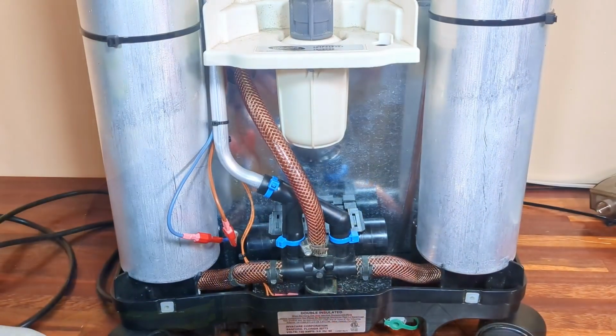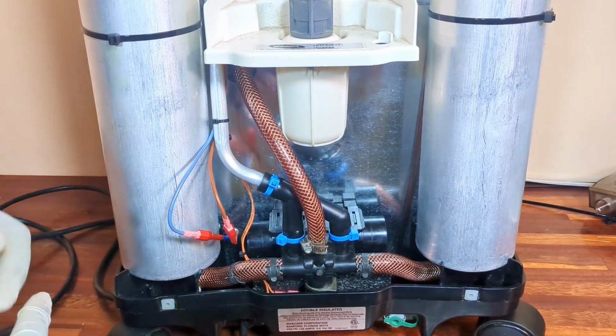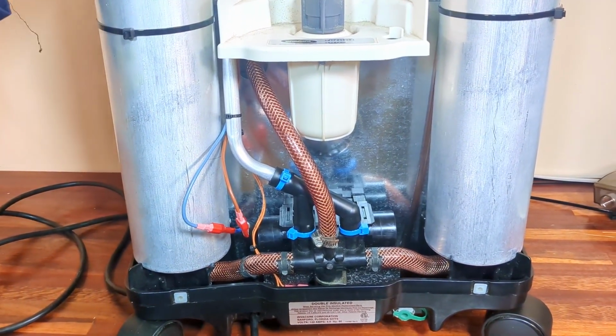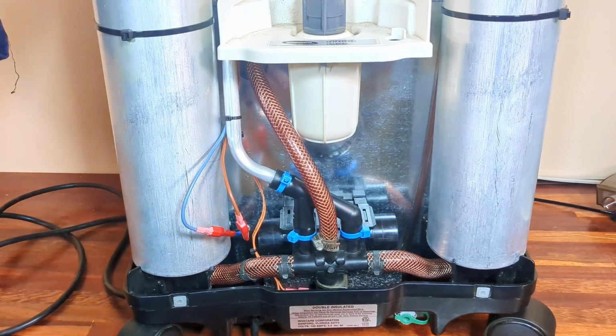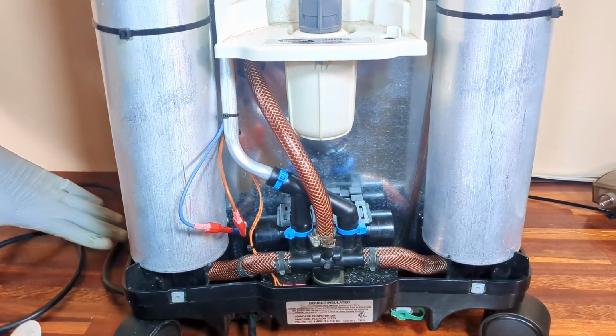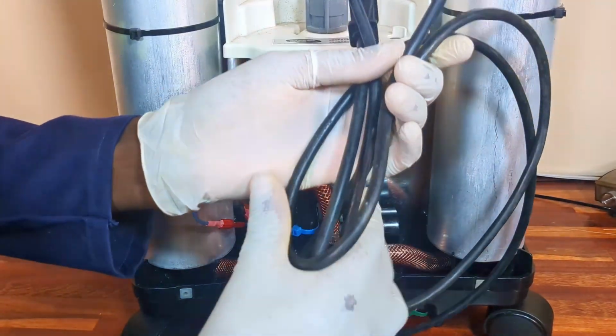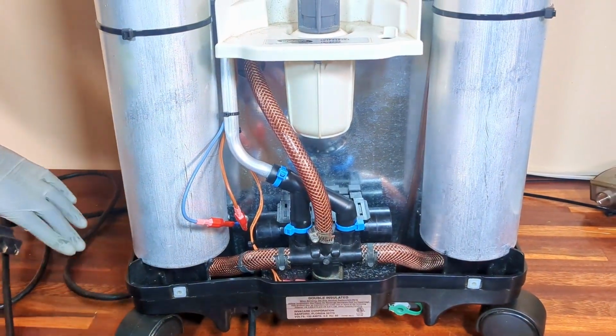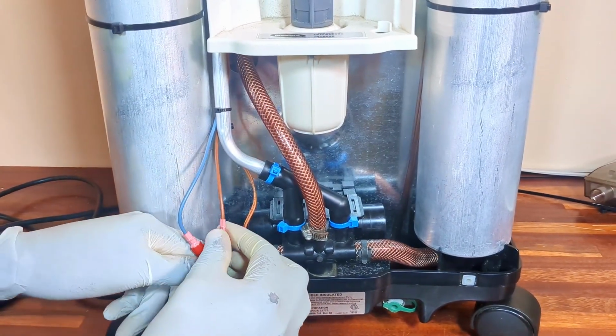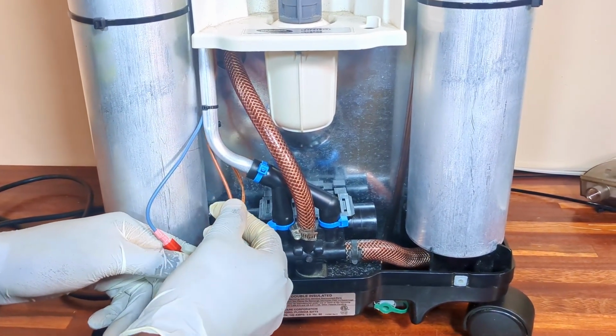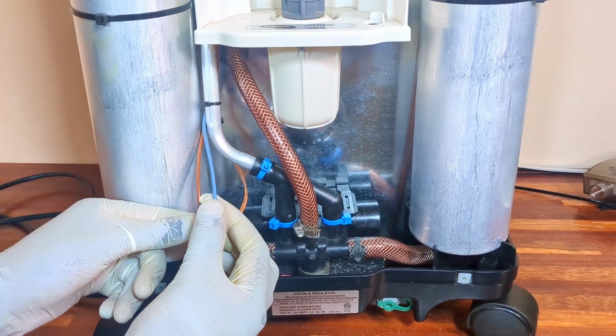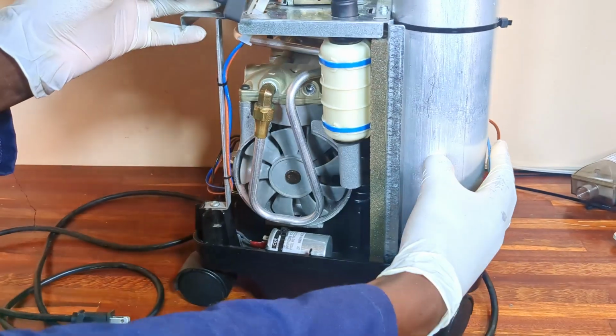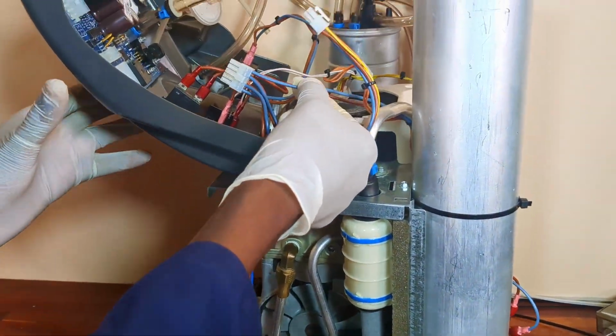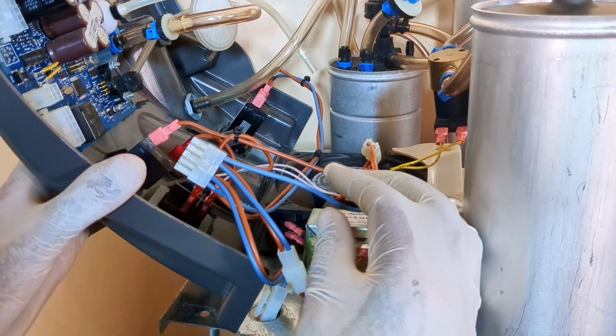Now I'll take you through the electrical system for this oxygen concentrator. As mentioned earlier on, this oxygen concentrator operates on 120 volts AC. This 120 volts AC is supplied to the unit by the power cord. This power cord has 2 cables, brown live, while the blue cable is the neutral. So this is the neutral cable I was talking about.